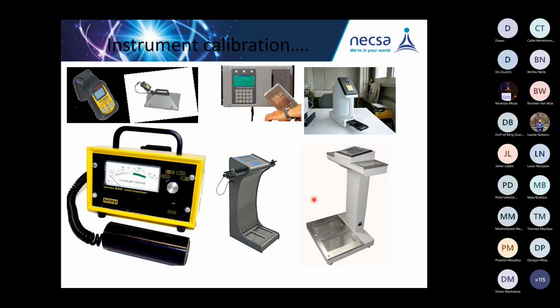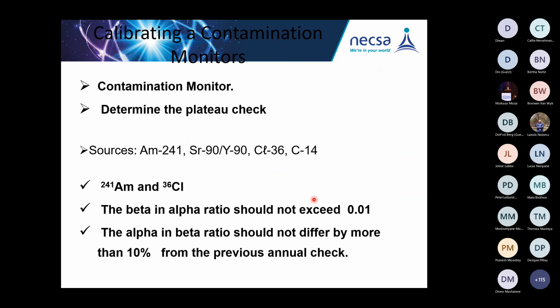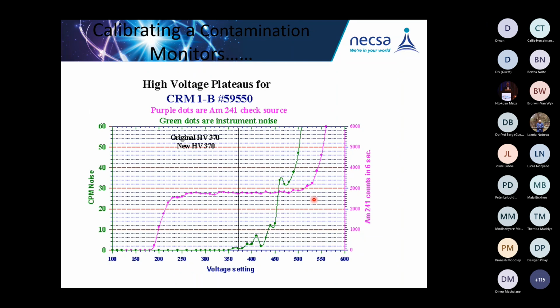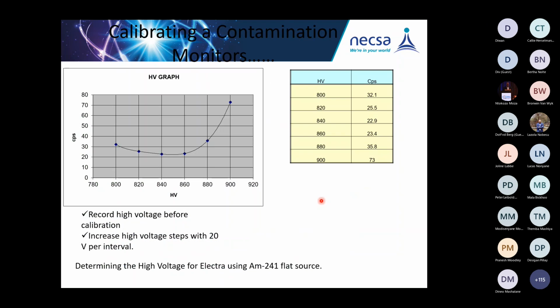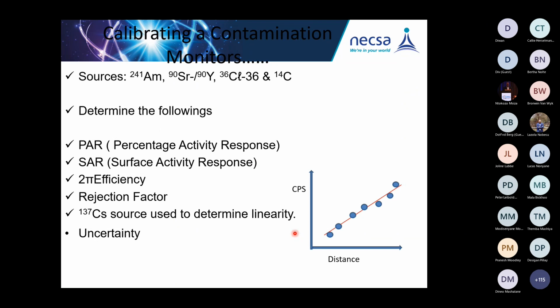Okay, right. Thank you. I will check my uncalibrated chronometer to make sure that I'm within the time. Okay, this is the high voltage plot that we determine when we perform the calibration, and then we set according to the data. And that is why we emphasize that this should not be changed. Even here, we set this one at 840 volts. And these were the count rates which we actually determined, using nuclides to determine that. We also perform the linearity with the cesium source.